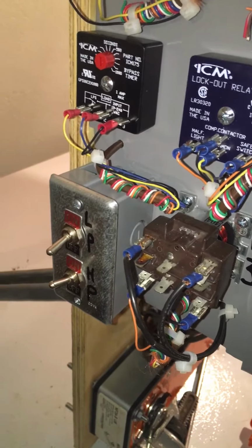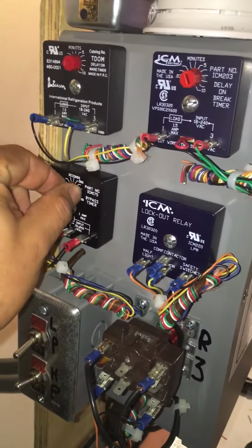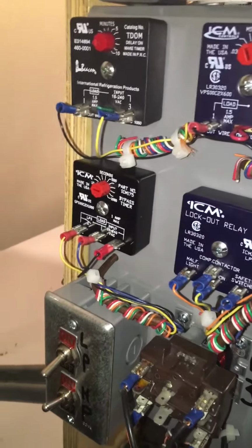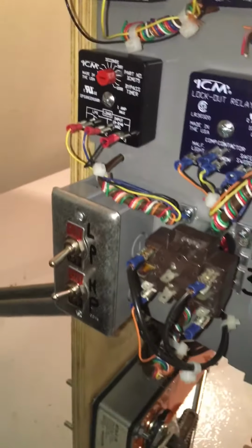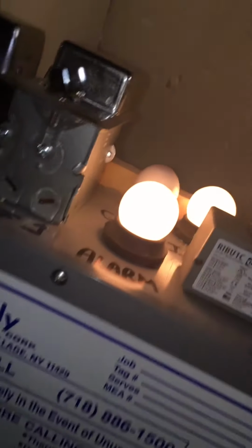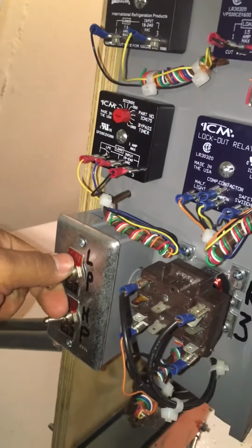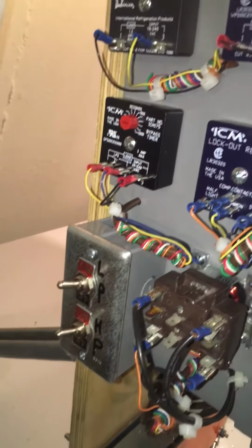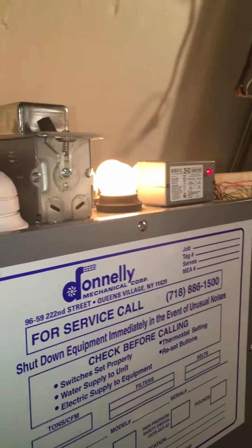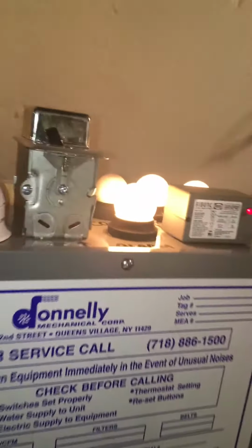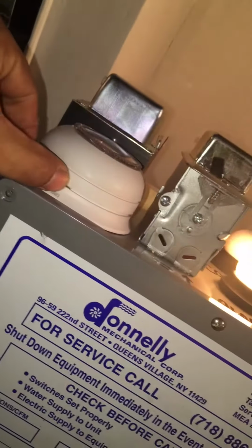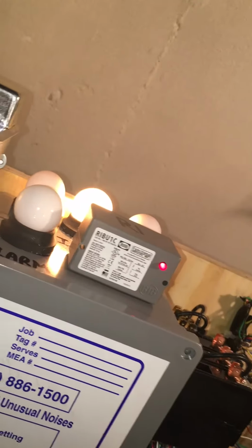And we stay active at the moment. Once I lower the bypass timer, we should start going into alarm off of the lockout relay, energizing the R3 relay. And there we go. Our compressor just turned off and our alarm light just lit up. Typical of the lockout relay, if we close back the low pressure switch, we still remain in lockout. So to de-energize the relay, we just kill the cooling circuit and then we turn it back on.